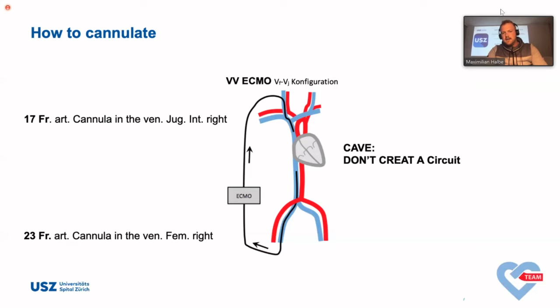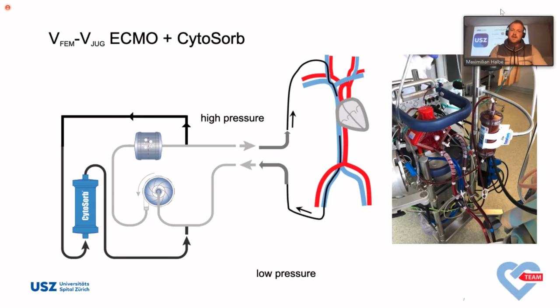We bring out the blood for the adsorber after the oxygenator, because there's the highest pressure. So you can have it like a bypass, and you can give the blood back before the pump, where you have the low pressure, most of the time the negative pressure. For sure, there is an off-label use, because if you use, for example, the CardioHelp system, you need to change something in the circuit.